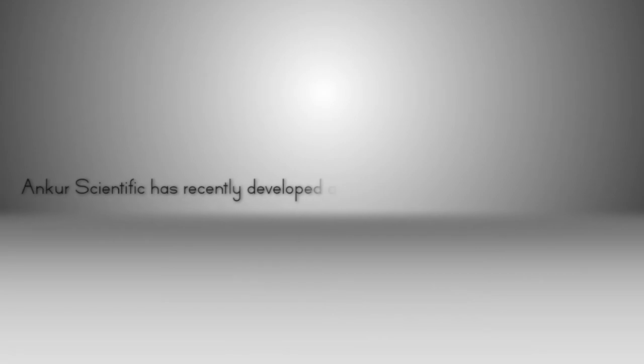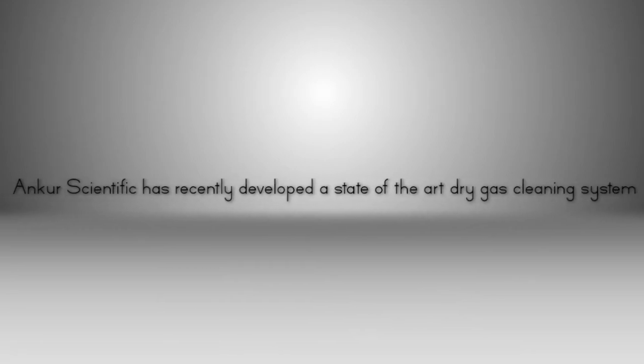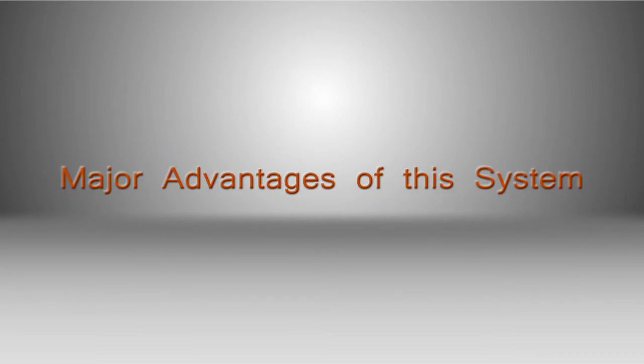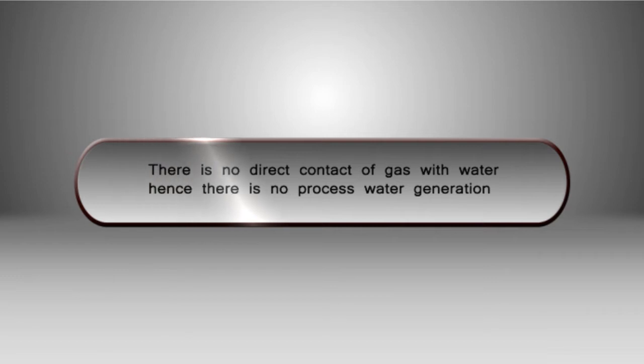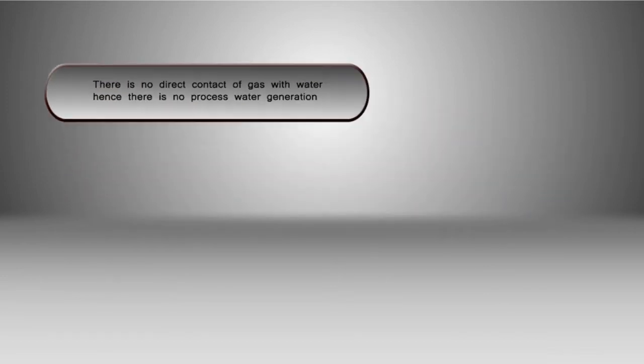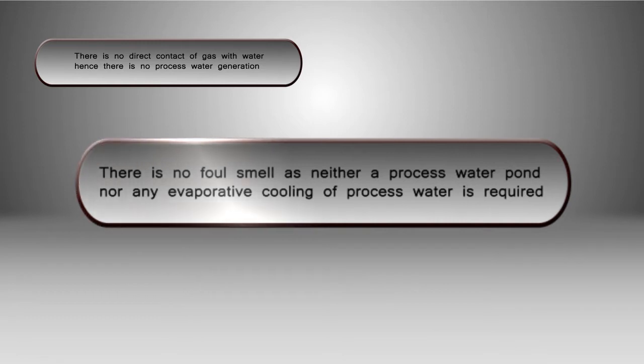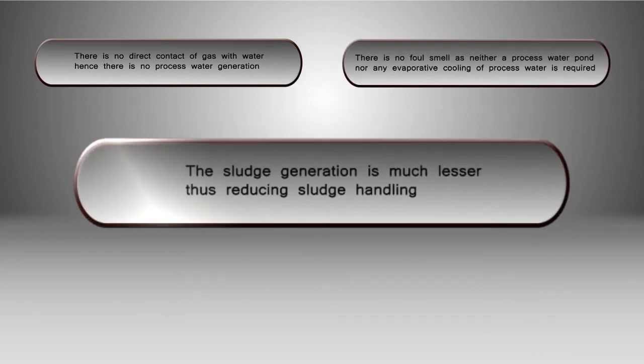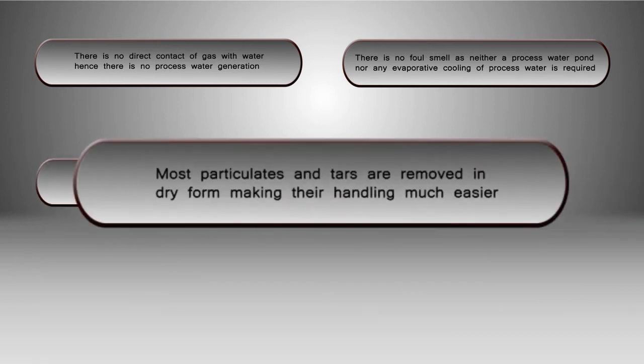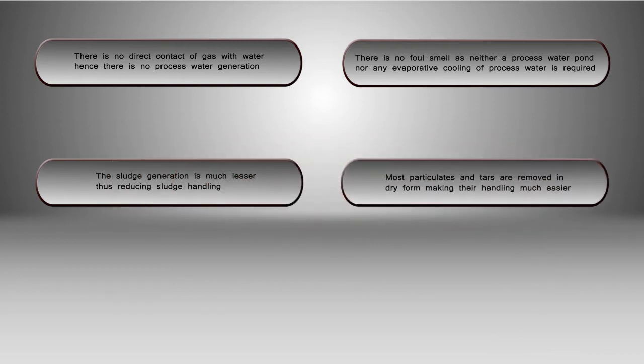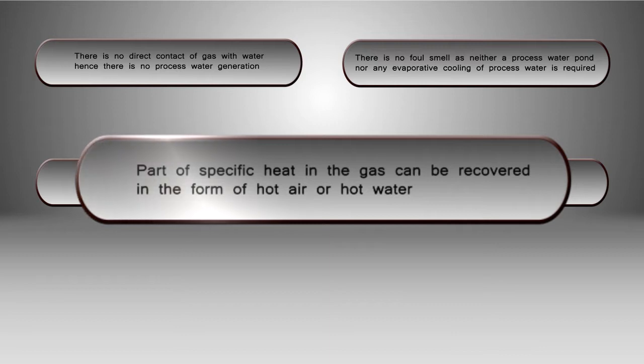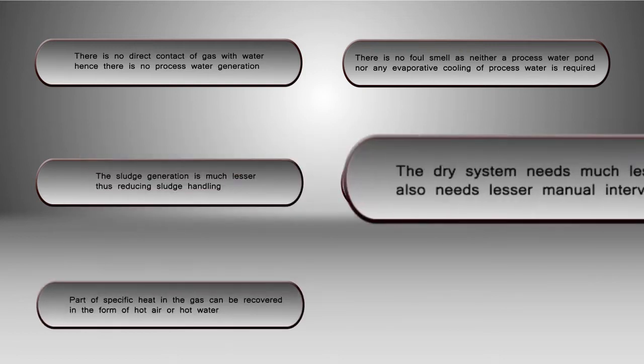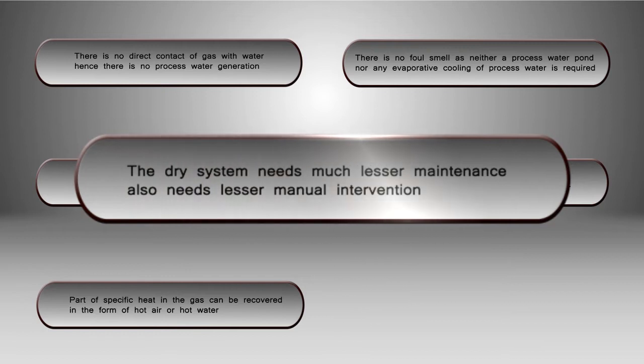Ankur Scientific has recently developed a state-of-the-art dry gas cleaning system. The major advantages of this system are: there is no direct contact of gas with water, hence there is no process water generation. There is no foul smell, as neither a process water pond nor any evaporative cooling of process water is required. The sludge generation is much lesser, thus reducing sludge handling. Most particulates and tars are removed in dry form, making their handling much easier. Part of the specific heat in the gas can be recovered in the form of hot air or hot water. The dry system needs much lesser maintenance and also needs lesser manual intervention.